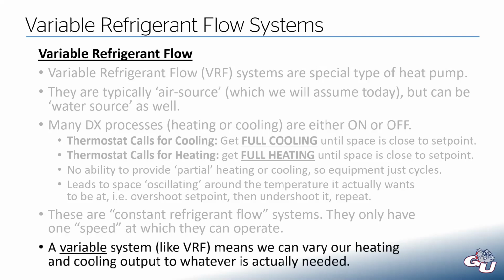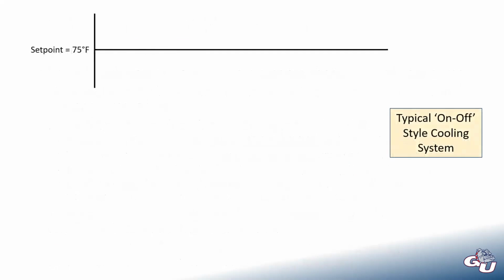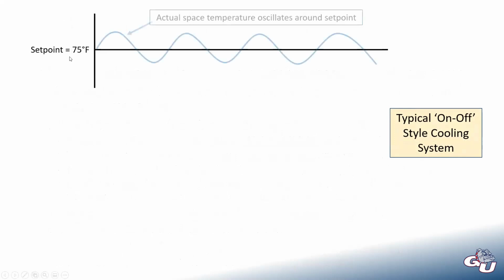But a variable system like VRF, it's right in the name, variable refrigerant flow, means we can vary our heating or cooling output to what that space actually wants. So let's say we had a typical on-off style cooling system. We are trying to maintain 75 degrees in our room. The actual space temperature is going to be something like that. We want 75 degrees, but we're not going to get exactly 75 degrees.